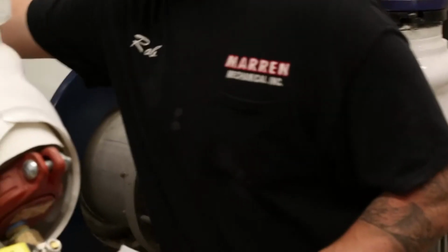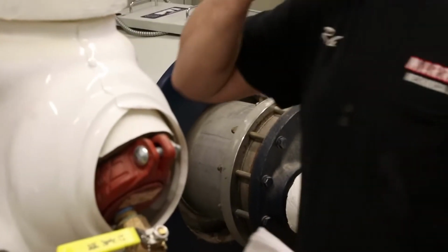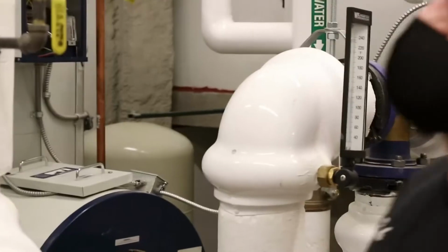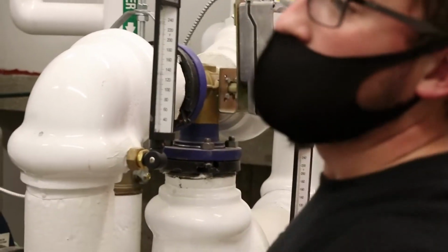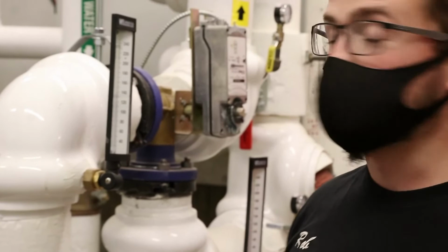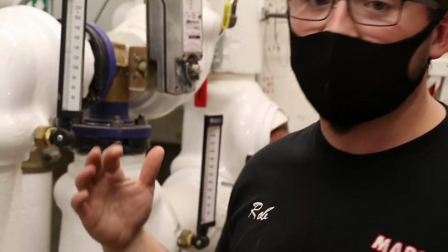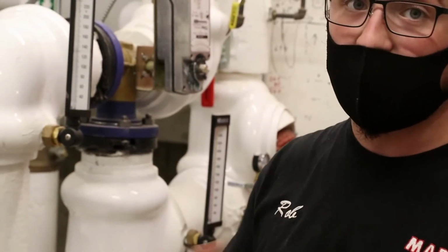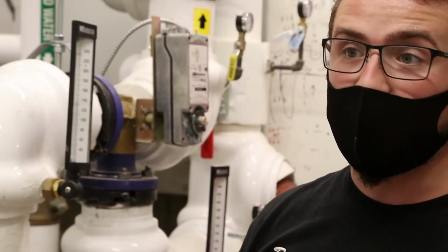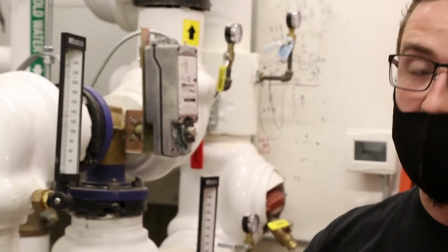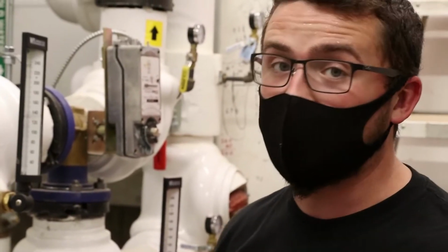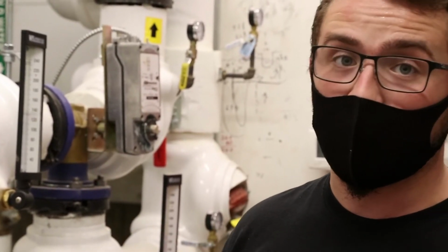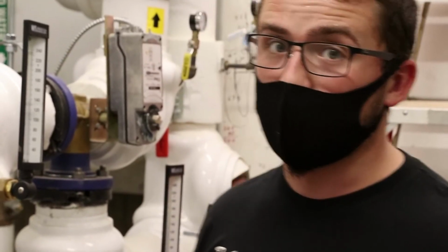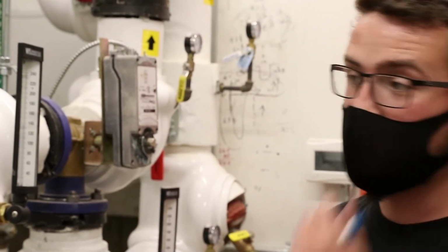That would include isolating the tank, draining the tank. Isolating means shutting off power to the tank first, then shutting off the cold water supply, shutting off the hot water supply. You would drain the tank 100% and then introduce cold water into the empty tank. This will hit the sides and bottom of the tank, stirring up the sediment. At that time, you can open the drain for about 10 seconds until water stops. You'll get dirty water out of there if there is sediment in the tank, and you would repeat until you get clean water. That would be a flushing procedure, which would only be done on an as-needed basis.